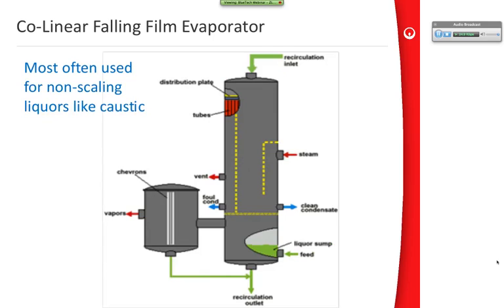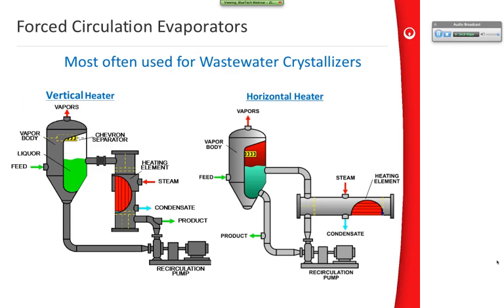There's another arrangement for falling film evaporators, which is generally used for non-scaling applications, non-seeded applications. This is a so-called collinear falling film, in which the vapor body is separated from the evaporator tube bundle, basically. And this has some advantages in non-scaling applications, but typically for scaling applications, it's not as favorable. Forced circulation evaporators are generally used for the crystallizing duty in ZLD systems.